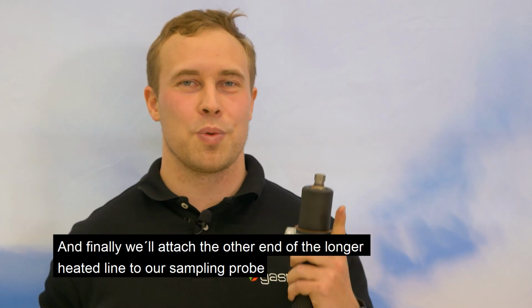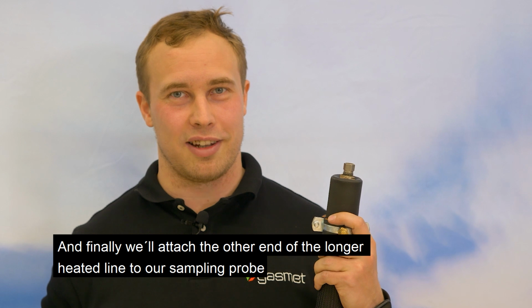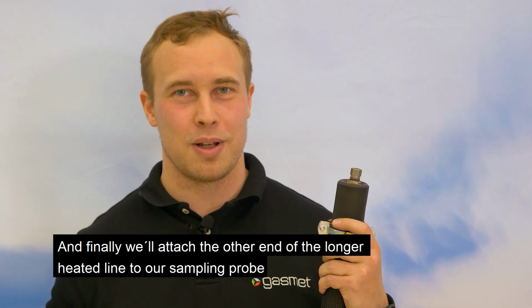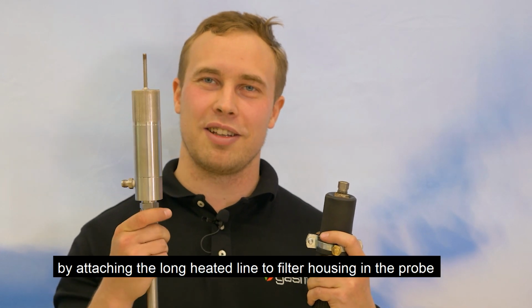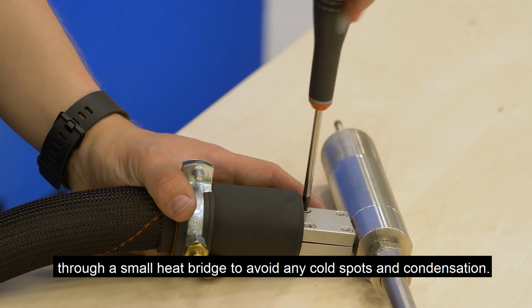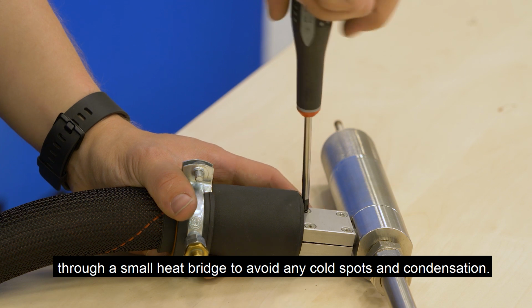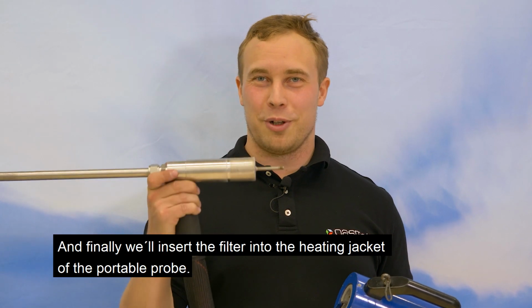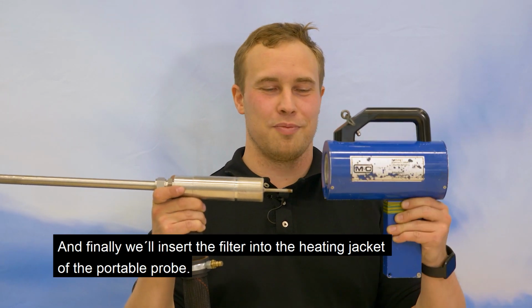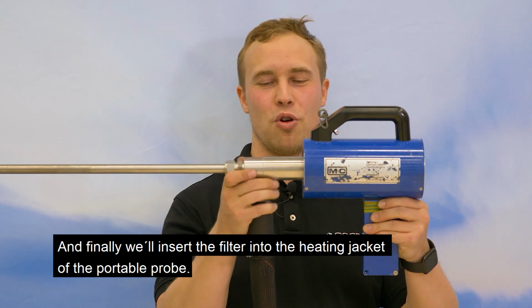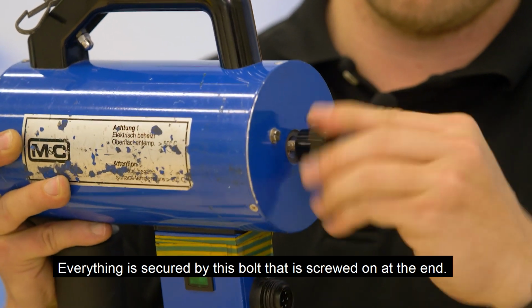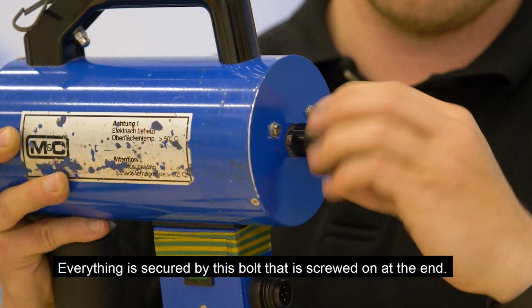And finally, we'll attach the other end of the longer heated line to our sampling probe by attaching the long heated line to the filter housing in the probe through a small heat bridge to avoid any cold spots and condensation. And finally, we'll insert the filter into the heating jacket of the portable probe. Everything is secured by this bolt that is screwed on at the end.